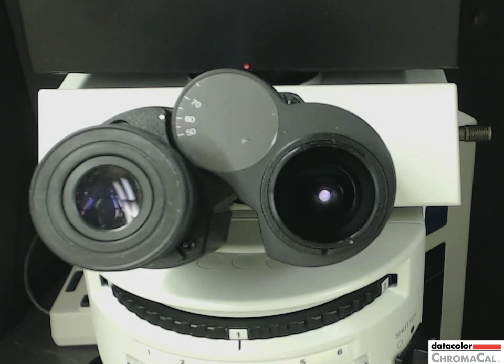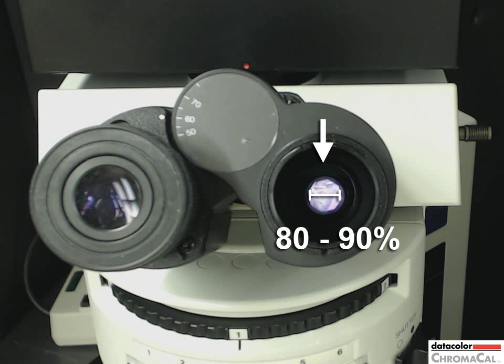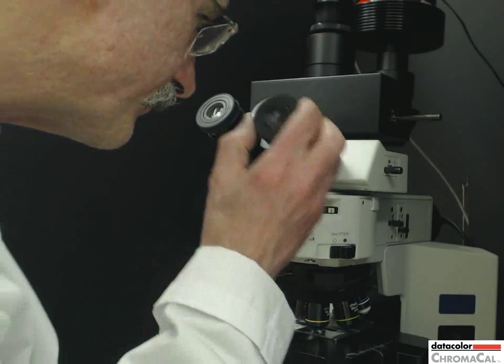Here's what you'll see when looking into the eyepiece chamber. Close the aperture until it allows 80 to 90 percent of the image area through, as seen here. Put the eyepiece back into its chamber.